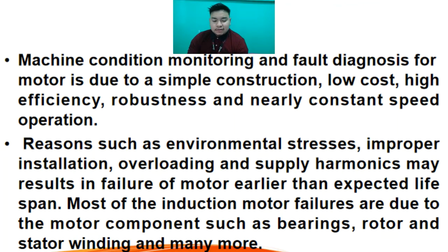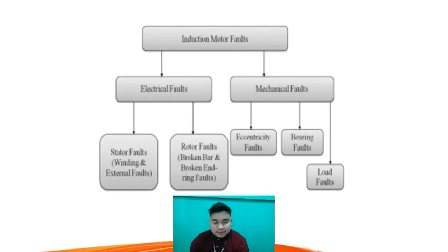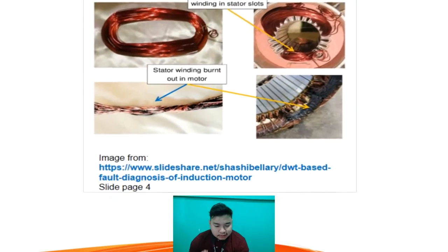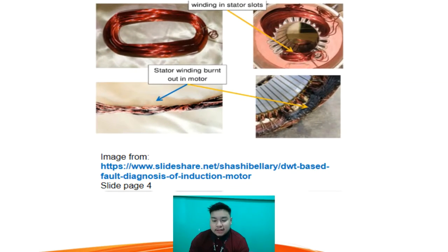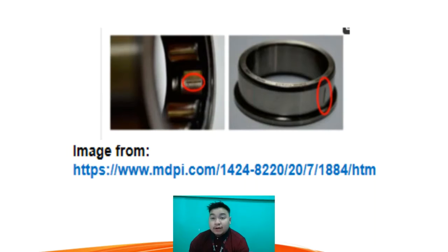The various faults in induction motors are broadly categorized as either electrical or mechanical failures, including stator winding defects, broken rotor bars, air gap eccentricity, misalignment, and bearing or gearbox failure, which is the most common type of failure as stated in figure 2.1. Motor faults have two categories: electrical faults, which include stator and rotor faults, and mechanical faults, which include eccentricity faults, bearing faults, and load faults.